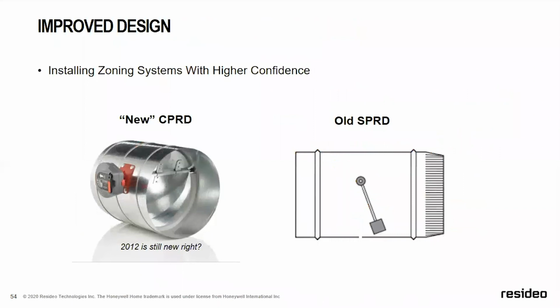So the difference between the old and the new, the SPRD had to be mounted level and horizontal, or it wouldn't work properly. There was a way to adjust the weight, but in our installation manual, it did say it should be horizontal and level. The new CPRD, well, 2012, it's still new. But this is a great bypass damper.